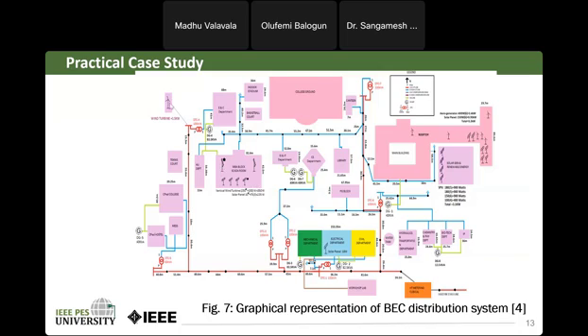The horizontal axis wind turbine is also shown, and in the SCADA room we can access complete communication from all seven distribution transformer centers. At each distribution transformer center we have an intelligent feeder control unit, the IFCU meter, which acts like a phasor measuring unit, commonly called PMU in industry.